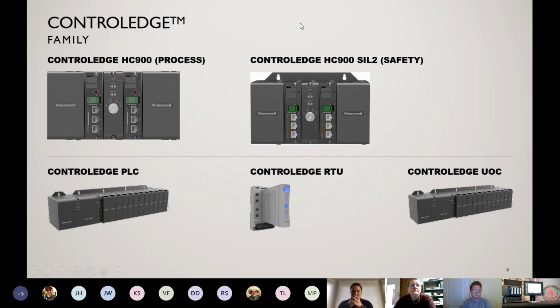So when we talk about the HC900, the HC900 is actually part of a family of products called ControlEdge. So the ControlEdge family includes the HC900 process controller as well as a SIL2 safety controller. These can be used in a redundant fashion or non-redundant. The two processor racks that I show here on this slide at the very top are for redundant applications. So you have two power supplies, two CPUs, and then a switchover unit in between them.